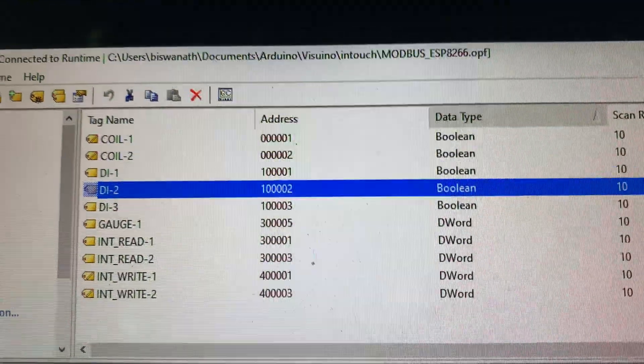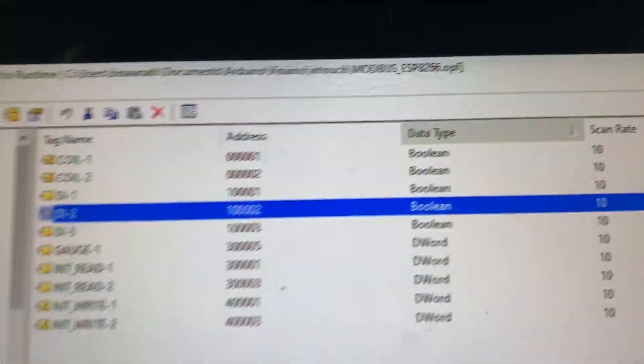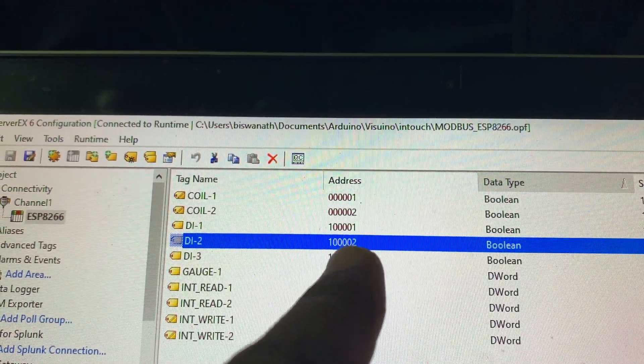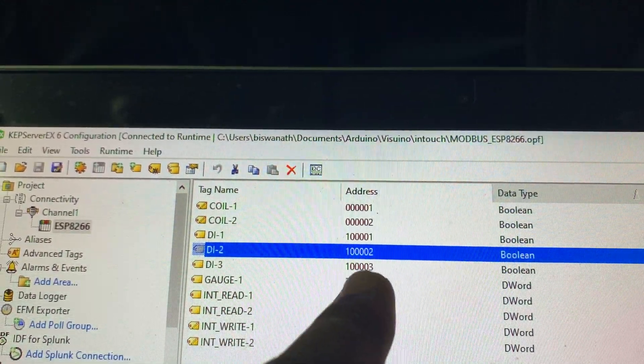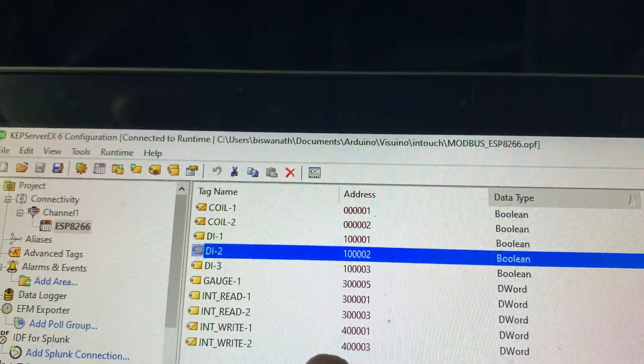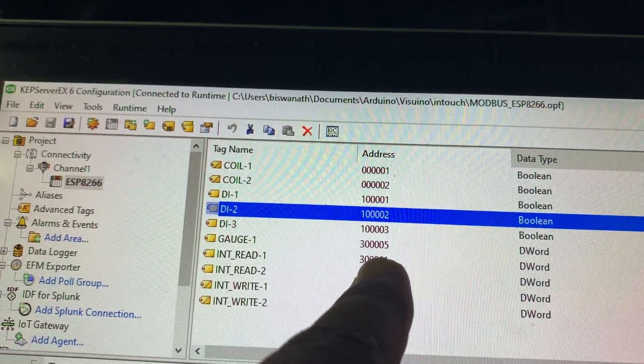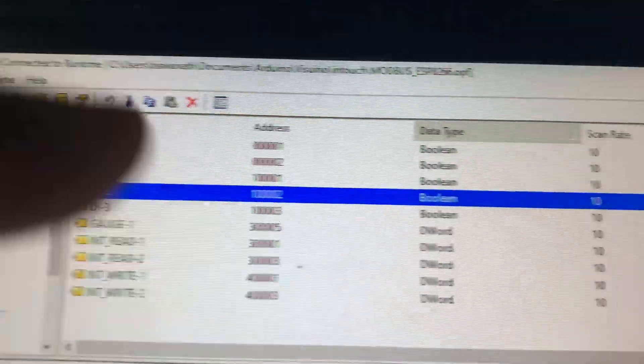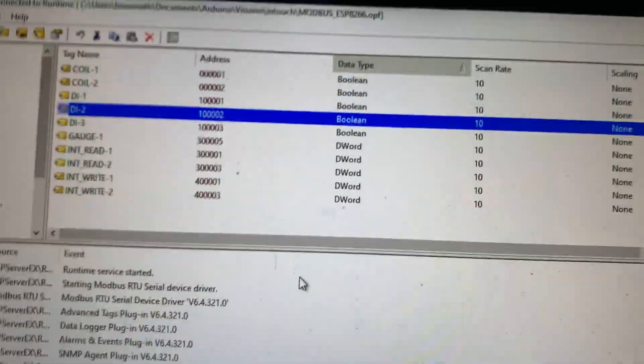You can see KEP server, I give here the address for each tag. I have mentioned the address. You can see for the coil I put 1, 2, for the DI-1 digital input 100001, 2 like this. Same for integer reading, read the value 30005 and write the value 40001 like this, it's double word.